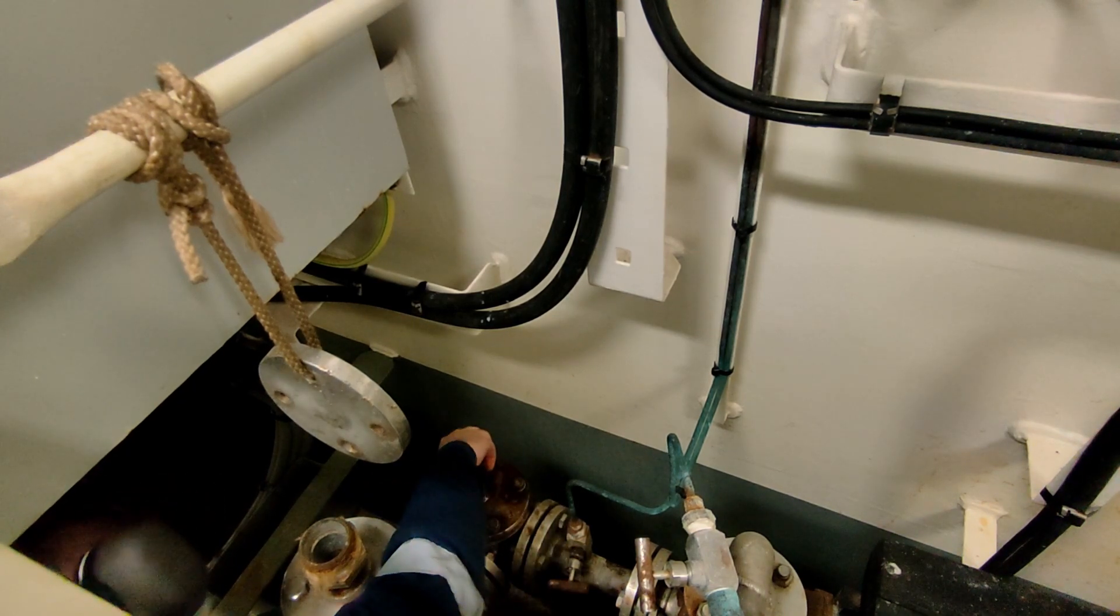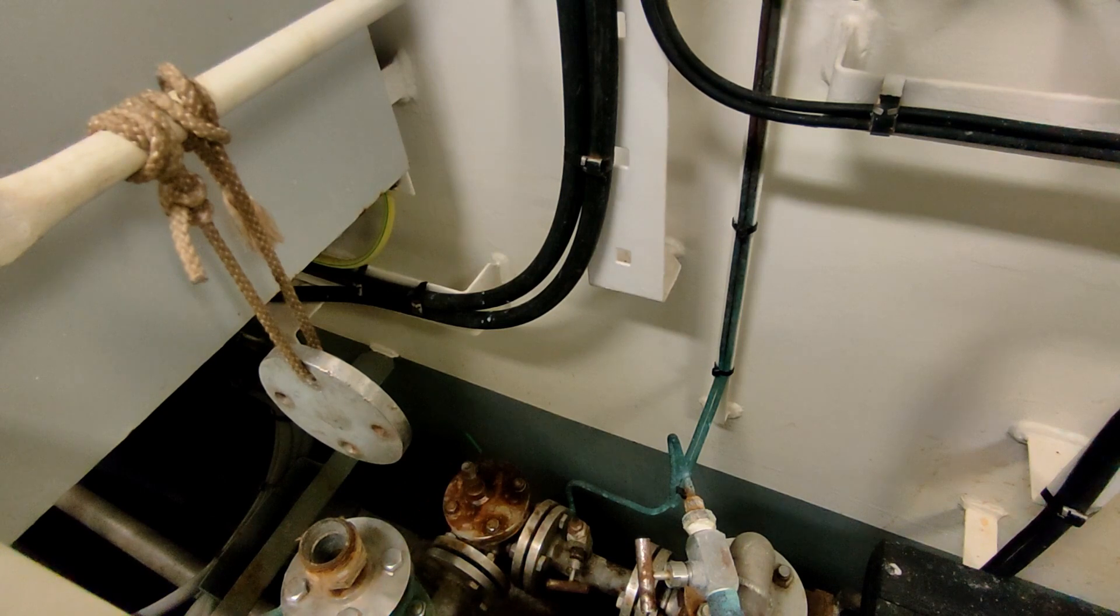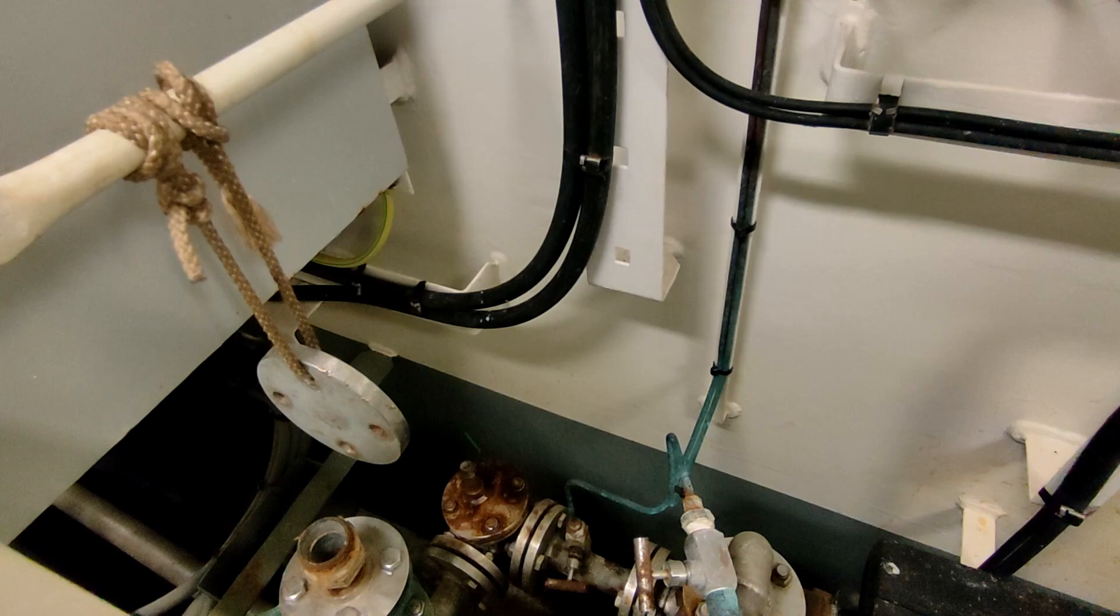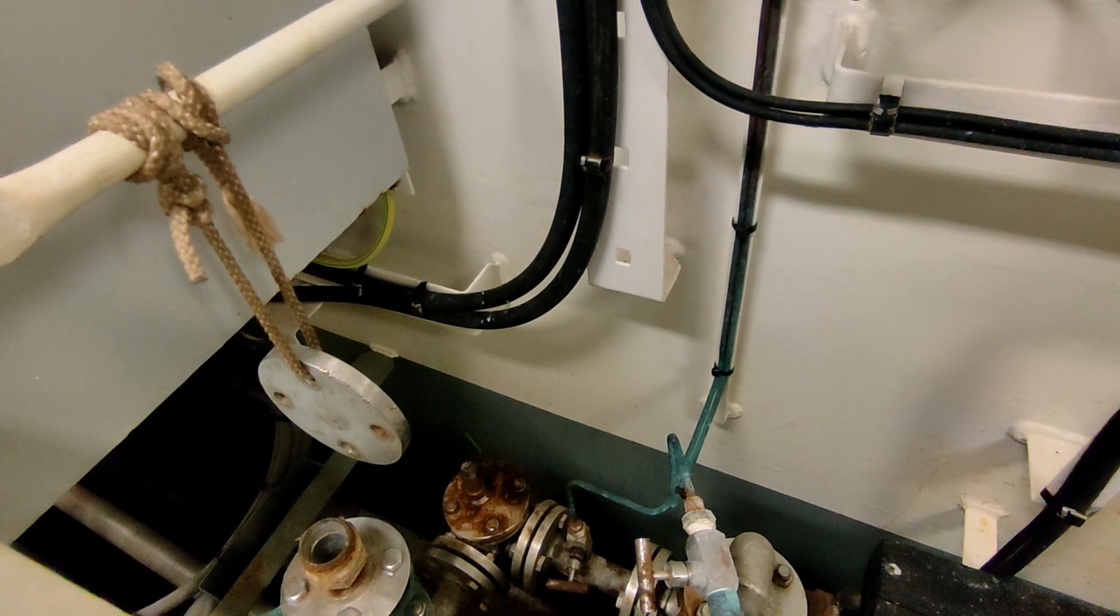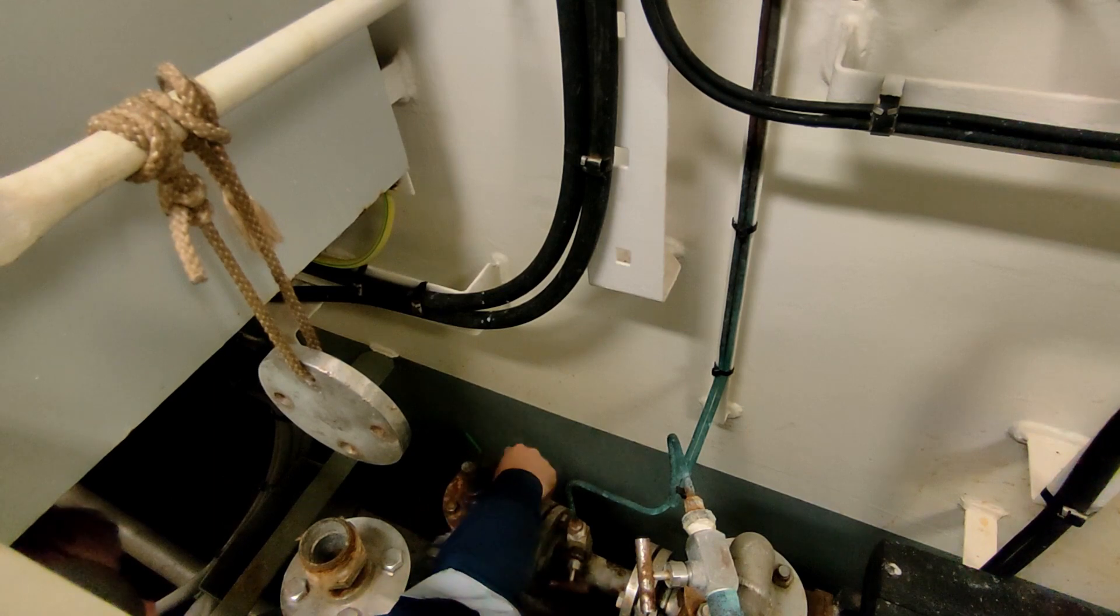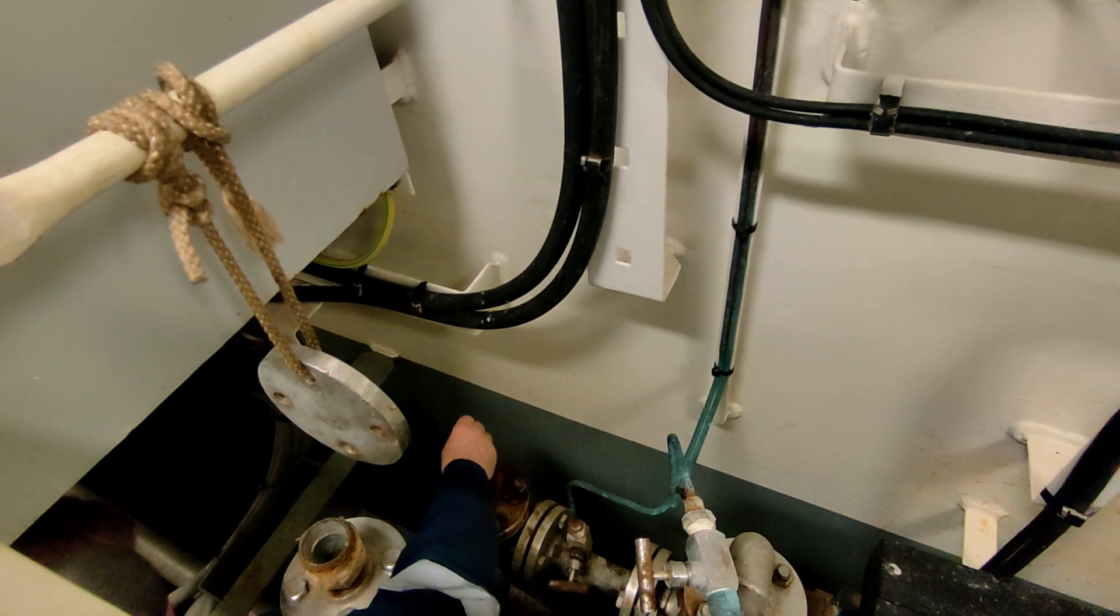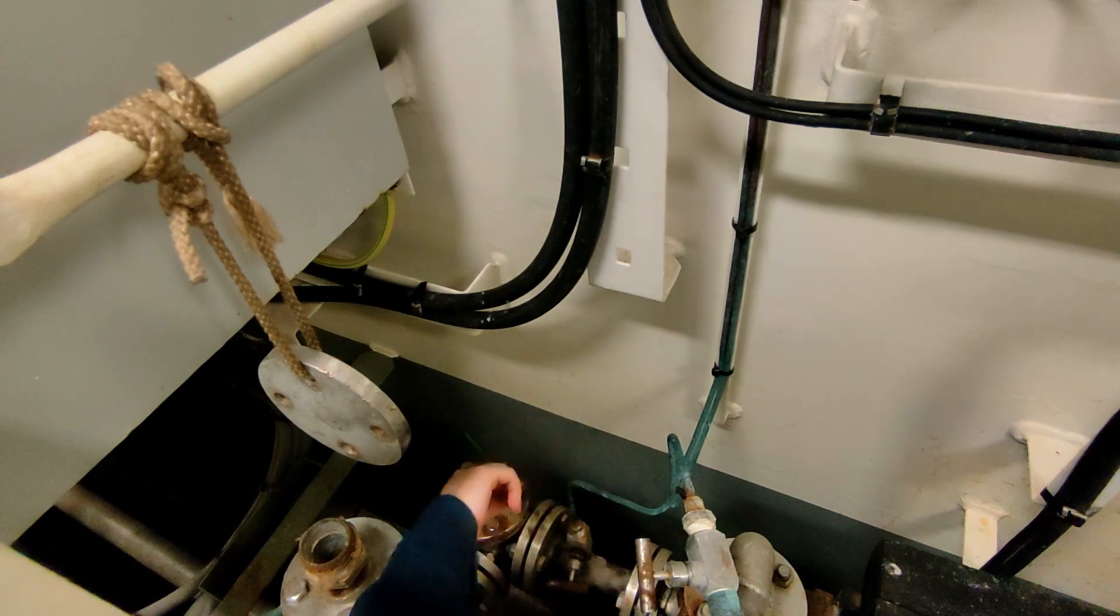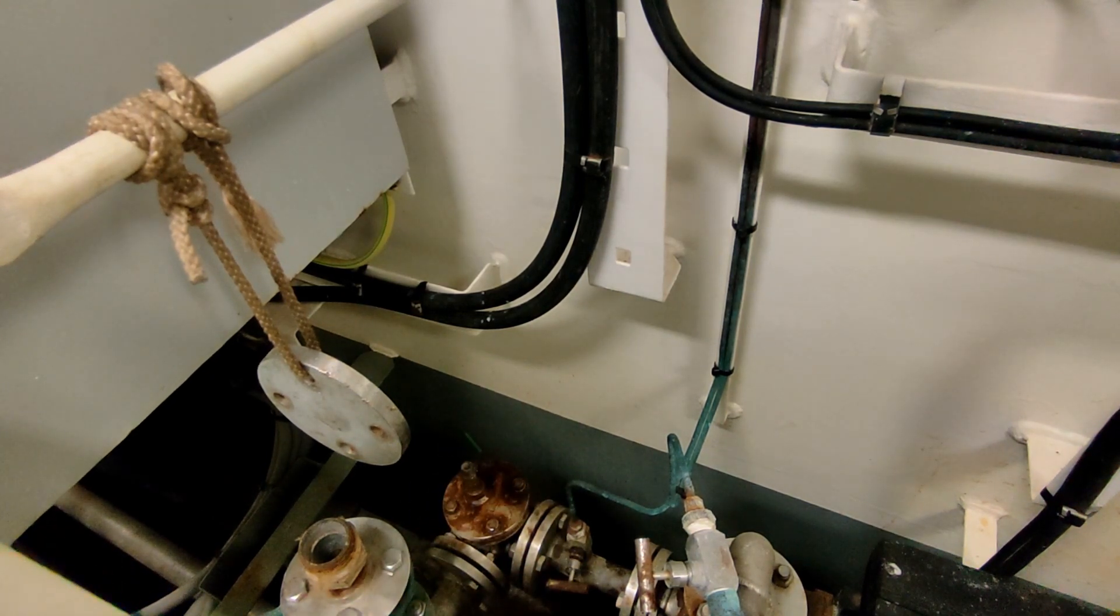So I'll close that valve for now and I'm just going to open the inlet valve so I can bleed off from the filter. So that's that open. You can see that there's no leaks coming from around here, so that O-ring's holding well. I'm just going to crack this valve, it'll come and vent the water, and I can close it again. And I'm not going to pull any air into my pump.